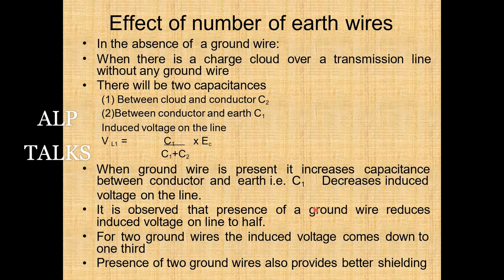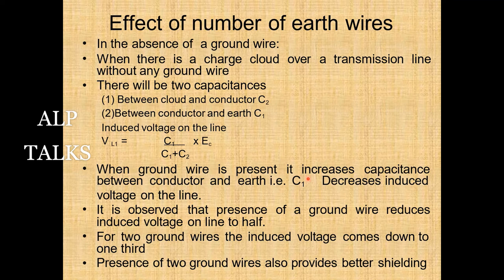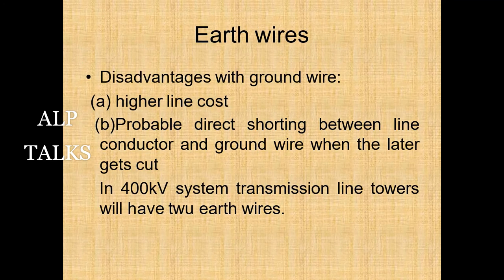Tower footing resistance shall be low, and shielding angle — the angle between the normal passing through the ground wire and the line joining the ground wire and outer conductor support points — shall be 30 degrees for 132 and 220 kV lines and 20 degrees for 400 kV lines. When a charged cloud is over a transmission line without any ground wire, two capacitances exist between cloud and conductors (C1 and C2), giving induced voltage = C1/(C1+C2) × Ec. With a ground wire present, C1 increases, and induced voltage reduces. With two ground wires, individual voltage comes down to one-third, and better shielding angle is also achieved.